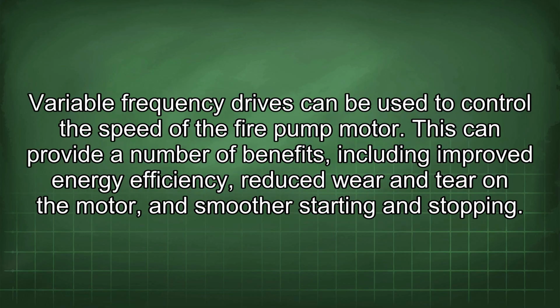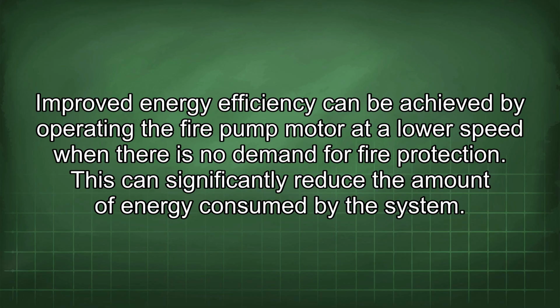Variable frequency drives can be used to control the speed of the fire pump motor. This can provide a number of benefits, including improved energy efficiency, reduced wear and tear on the motor, and smoother starting and stopping. Improved energy efficiency can be achieved by operating the fire pump motor at a lower speed when there is no demand for fire protection. This can significantly reduce the amount of energy consumed by the system.